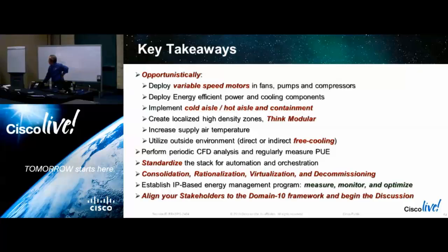The limit number is 25 kilowatts. If you're going to go above 25 kilowatts per rack, it makes an increasing amount of sense to go water to the rack, whether it goes in the rack or cold wall, whatever. There's a ton of technologies there. There are 100 vendors in that space that have different point solutions for it. At that point, there are two decisions around specifically what do you need and why, and then you can parse out which just makes sense. Roughly 25 kilowatts is fine. There's some little fuzziness.